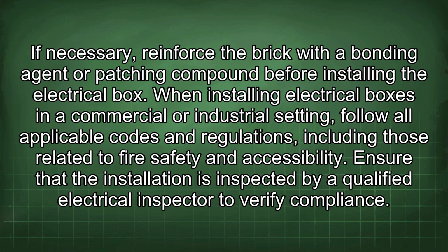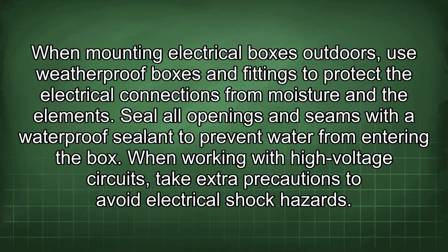When installing electrical boxes in a commercial or industrial setting, follow all applicable codes and regulations, including those related to fire safety and accessibility. Ensure that the installation is inspected by a qualified electrical inspector to verify compliance. When mounting electrical boxes outdoors, use weatherproof boxes and fittings to protect the electrical connections from moisture and the elements. Seal all openings and seams with a waterproof sealant to prevent water from entering the box.